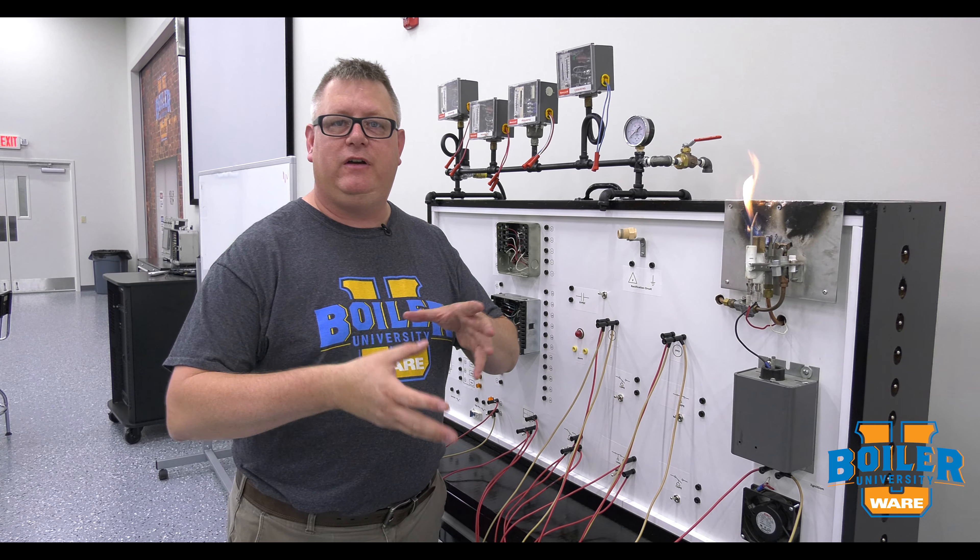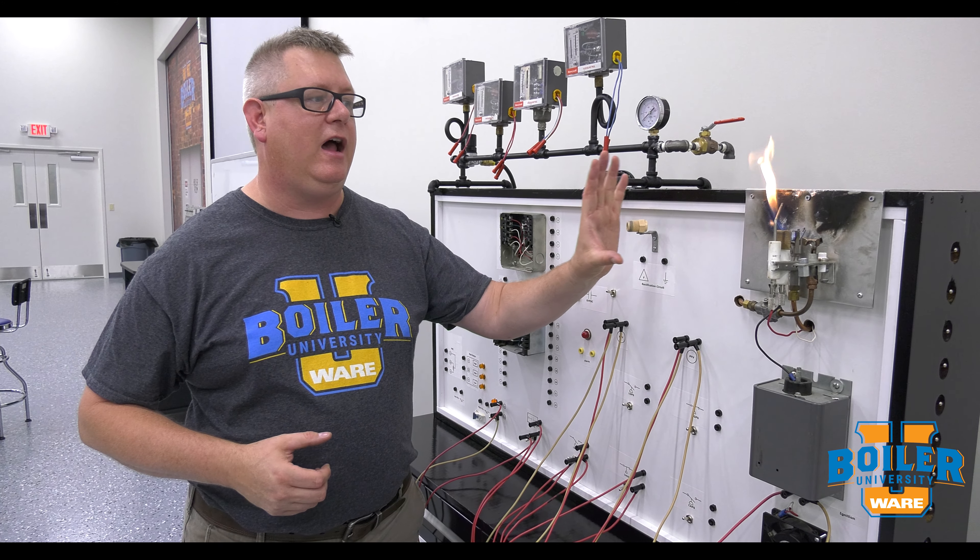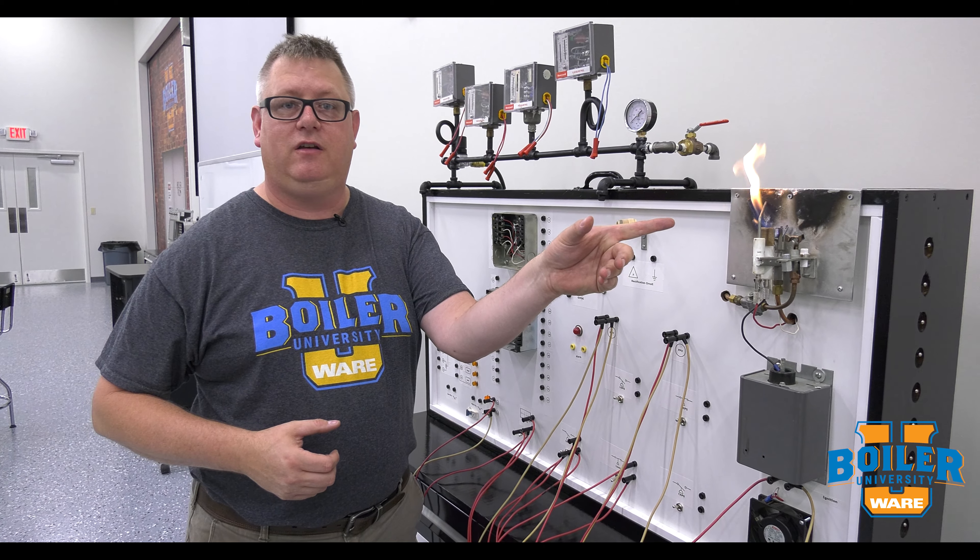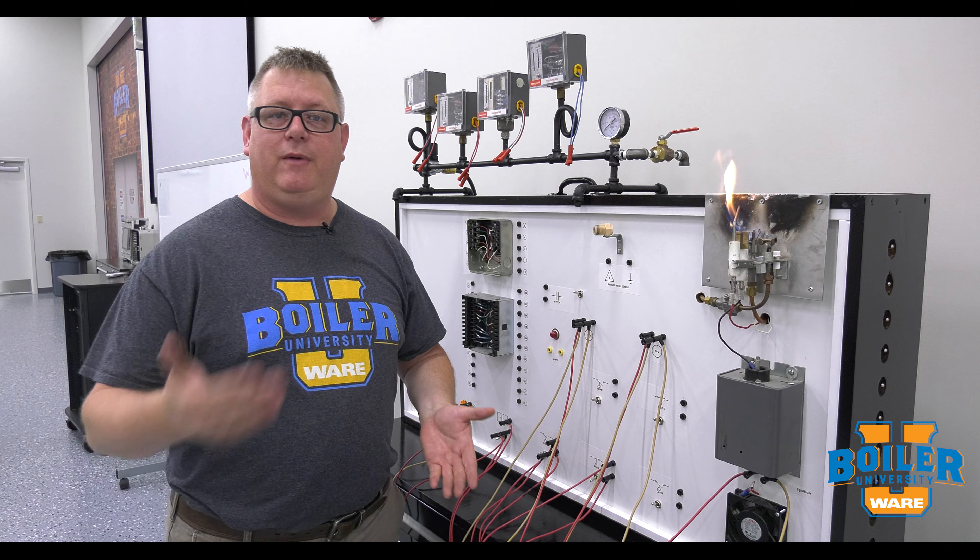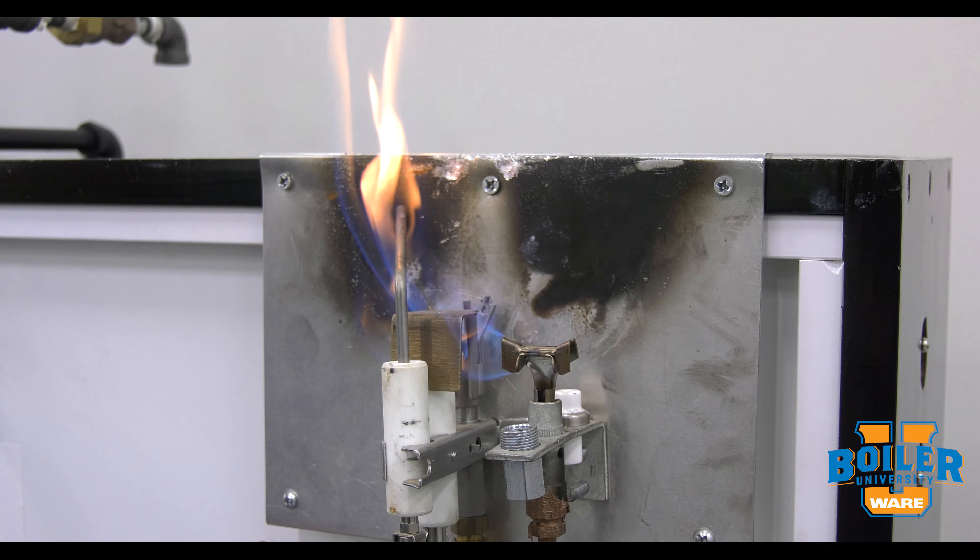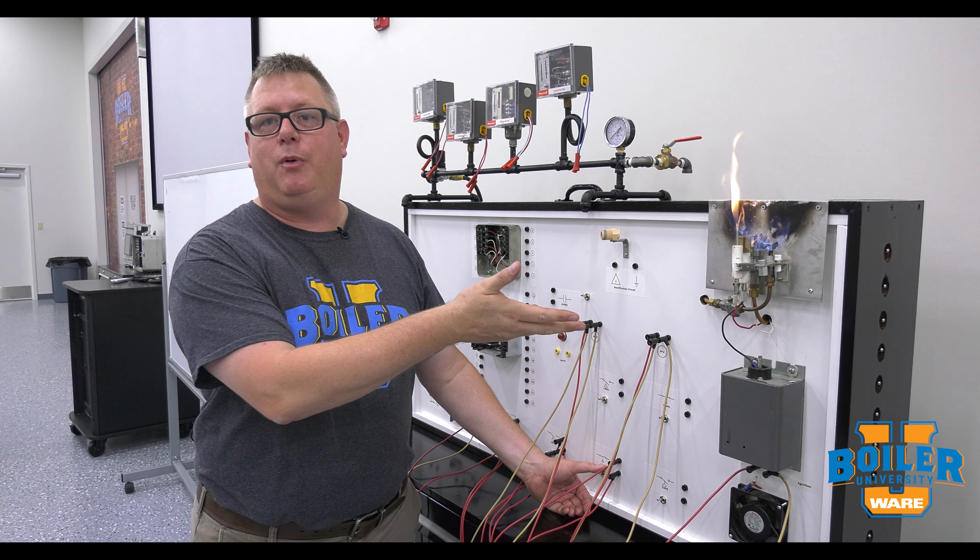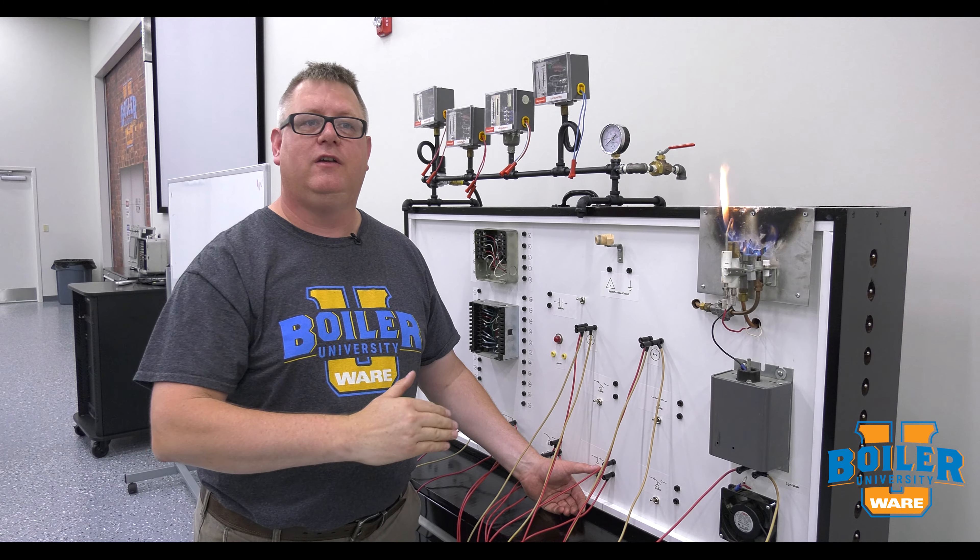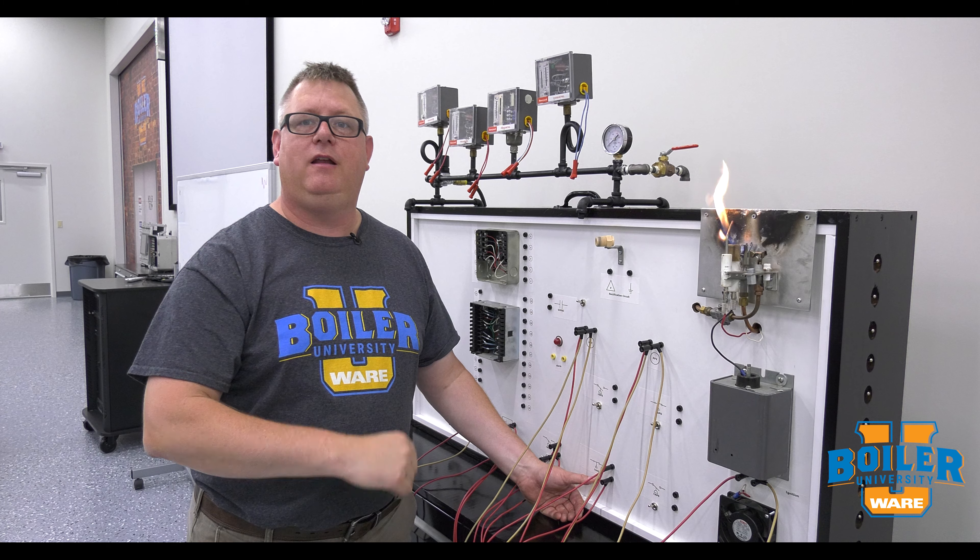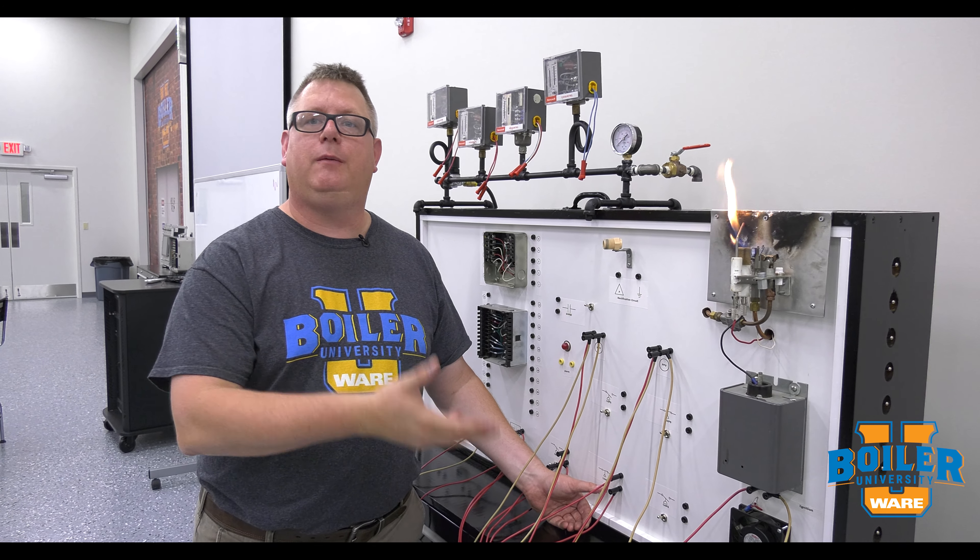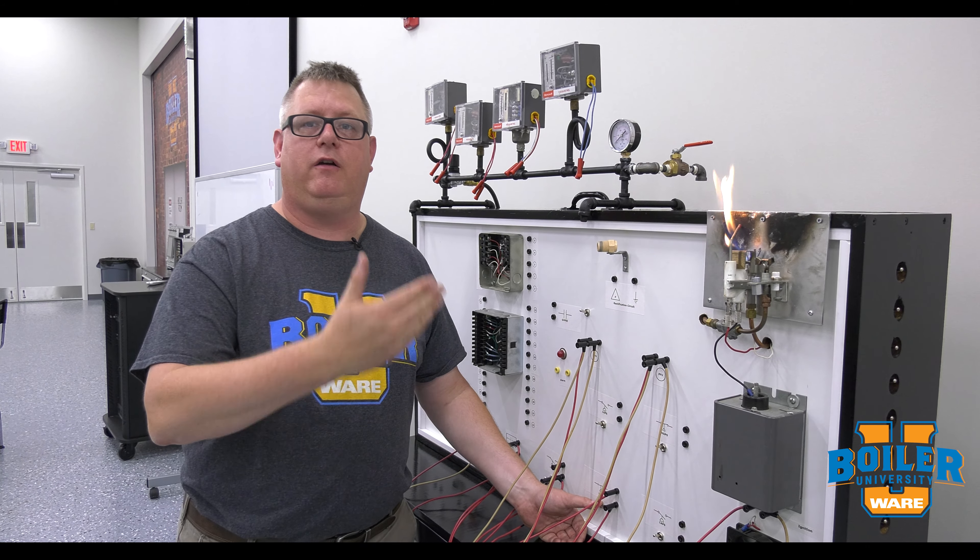If we have an atmospheric unit we'll often have a standing pilot and the pilot will stay lit at all times using a flame detection system to verify that it's lit. When we get a call for heat, the main fuel will simply be energized. There's our main fuel, a little bit anemic there but we get the point. When the call for heat is satisfied, the main fuel valve will shut off and the pilot will remain on. This is typical for an atmospheric unit that doesn't have a fan that has to start and stop.